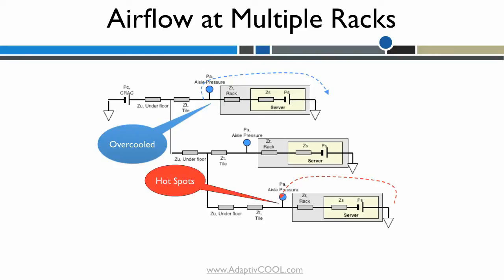At the third rack, the warm air from the hot aisle is pulled into the server leading to hot spots. At the first rack, the excess cold air spills into the hot aisle leading to wastage of cold air.